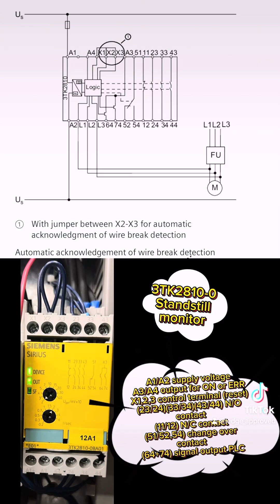Then we've got our X1, 2, and 3—there's your control terminals with your resets. Then we've got our three normally open contacts, one normally closed, and you've got a changeover like a relay going in there. As you can see with any safety relay, these are all mechanically connected, so if one was to have an auxiliary going out saying safe, you can't have your contacts welded shut and then the machine saying it was safe.